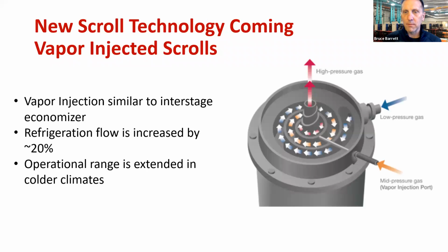How does it look? Well, the compressor simply has a port in the side, like an interstage economizer. It takes mid-pressure gas and re-injects it into the compressor so it can keep spinning and pushing the heat of compression up. Increases the refrigerant flow by about 20%, but it greatly extends the operating range in those colder climates.